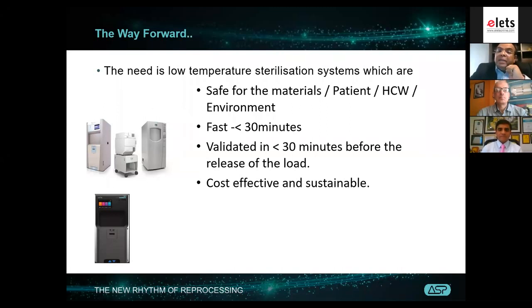You can't dip it in any chemical sterilant like glutaraldehyde or ortho-phthalaldehyde, because that will affect the working of the filters. So now it's not only the robustness of sterilization that's needed, it's also whether the machine is able to take care of a fragile environment and fragile materials.